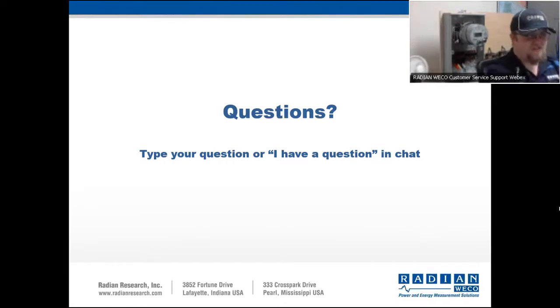So would it make sense to start a test procedure with demag? Not particularly. Typically, what I would recommend is what I suggested earlier, which was get an as found result, see what it is first before you start running the demag. So if you have A, B, and C phase CTs, depending on what those read as found, that's when you can then decide, okay, do I want to run the demag or do I want to skip that, and do I think this site's okay as is? So I wouldn't start with it, but I would run it based off of what you see on an as found test and what you see when you first get on the site.